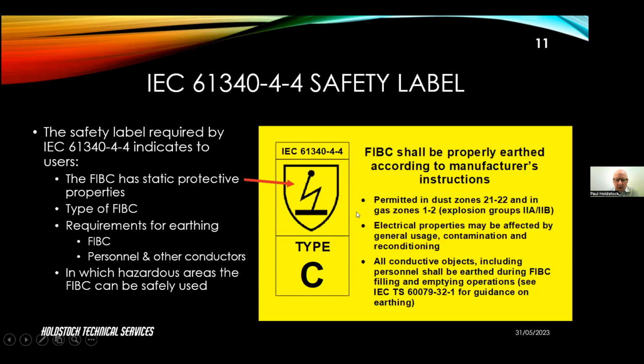First of all, there's an indication that the FIBC has static protective properties. Anytime you see a shield on a label, that means it's providing protection against a certain hazard. In this case, the little lightning flash indicates that it's providing protection against static electricity. The type of the FIBC is clearly displayed, in this case, a type C. And then the requirements for earthing, both of the FIBC itself. There's a statement there that says the FIBC shall be properly earthed according to the manufacturer's instructions, and also that personnel and other conductors need to be earthed. And again, there's a reference back to the IEC 60079-32-1 that gives more guidance on the requirements for earthing.